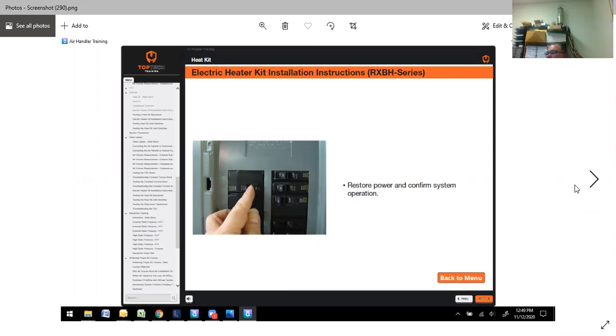And then as a byproduct of that, if I'm using a heat pump, I want to bring in my heat pump, and then I want to kick in the auxiliary heat with it. So then I'll have both the heat pump and the emergency or the auxiliary heat, and I want to use my meter to verify each element comes on, each element comes off. They make it pretty simple. Do that on startup. If you do that, it'll save you lots of trouble. I've had guys, even my own installers, I had to train them to do that operation, because invariably something would be wrong, and then I get the call back and, you know, emergency heat's not on or auxiliary heat's not working.